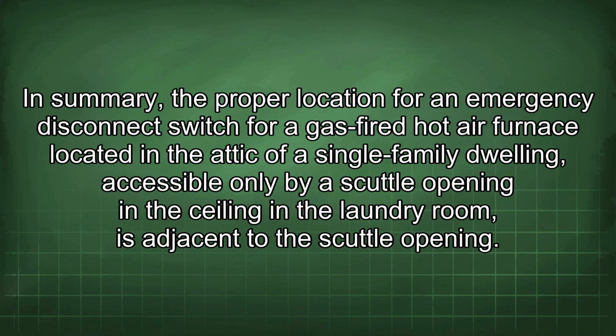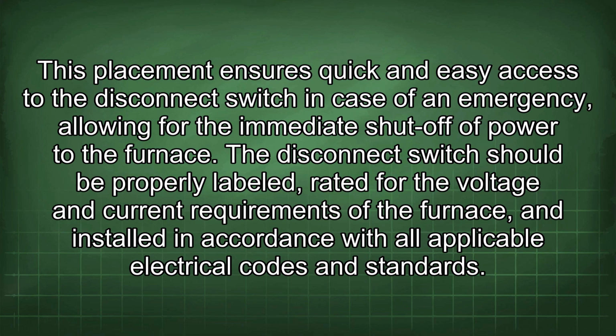In summary, the proper location for an emergency disconnect switch for a gas-fired hot air furnace located in the attic of a single-family dwelling, accessible only by a scuttle opening in the ceiling in the laundry room, is adjacent to the scuttle opening. This placement ensures quick and easy access to the disconnect switch in case of an emergency, allowing for the immediate shut-off of power to the furnace.